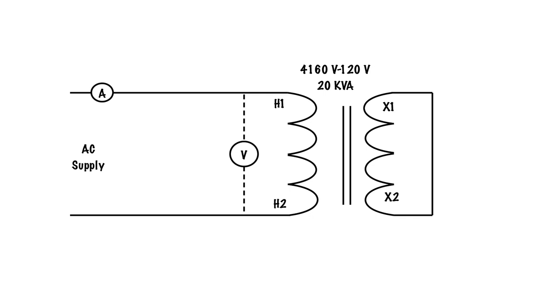In this video, we're going to discuss how to calculate the percent impedance of a transformer using what is called the short circuit test. Now, in my over 20 years in the trade, I've never actually done this test out in the field. I've done it as a teacher in a classroom. So it's something that's not very practical, but it is a good example of how we come up with that number for percent impedance.